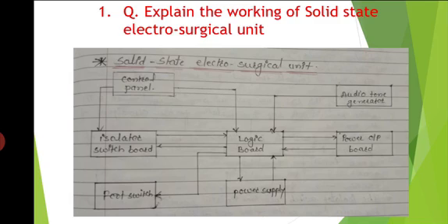The 250 kilohertz signal used for cutting is given to the power output, where it controls the push-pull parallel power transistor output stage. The output of this high power push-pull amplifier is applied to a transformer, which provides voltage step up and isolation for the output signal of the machine.